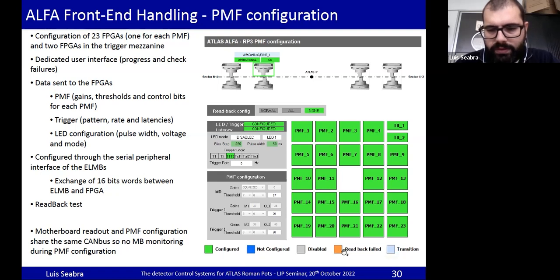In case the readback fails, we get an orange indicator, and we are configuring the PMF, so we have information coming from this panel. During this configuration, we cannot perform motherboard monitoring, because we use the same CAN bus cable for monitoring the motherboard and for configuring it. CAN bus doesn't like having different configuration information coming at the same time, so we'll get some noise and the configuration will not work.